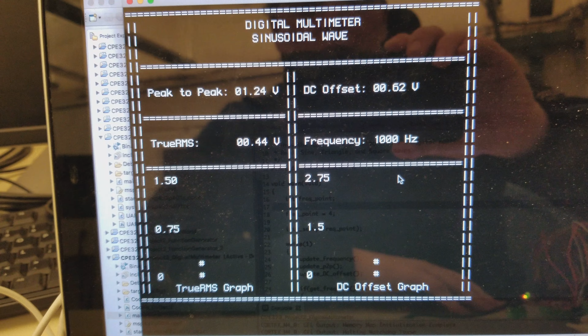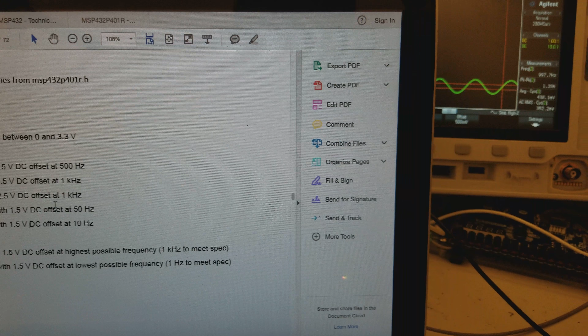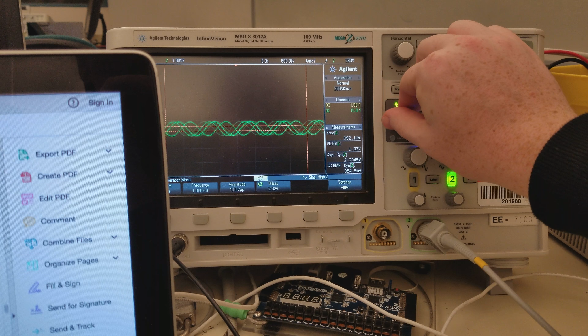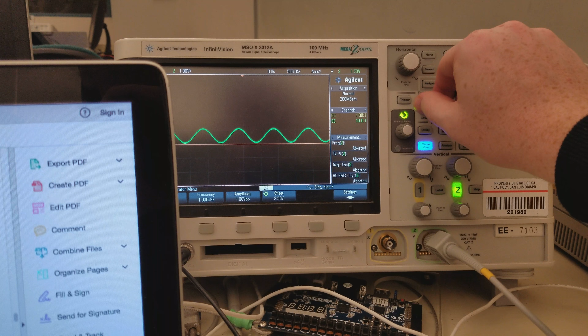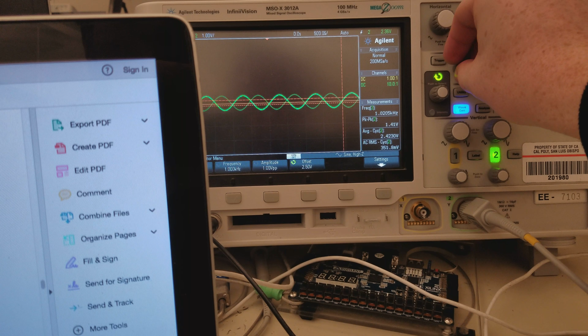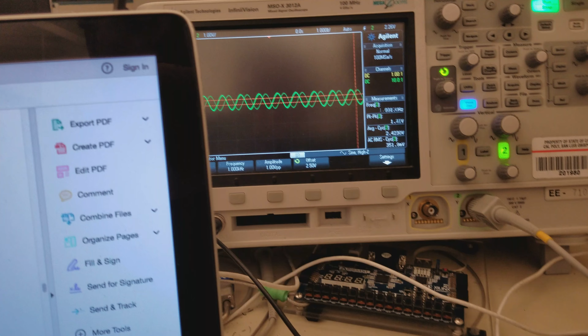And as we see, we have a 1.5 volt DC offset, 1.59, 1.6. We have the peak-to-peak, about 3.2, 3.11, which if we look at the peak-to-peak being read on the oscilloscope, it's pretty accurate. True RMS at 1.12, which we see on here, 1.06. The frequency at around 500 hertz, sometimes it goes up to 512, and we have our graphs displaying true RMS and DC offset. And then up here we have it displaying a sinusoidal wave.